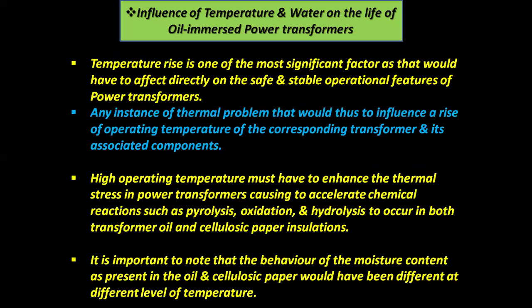Now, influence of temperature and water on the life of oil immersed power transformers. Temperature rise is one of the most significant factors, as it directly affects the safe and stable operational features of power transformers. Any instance of thermal problem would influence a rise of operating temperature of the corresponding transformer and its associated components. High operating temperature enhances the thermal stress in power transformers, accelerating chemical reactions such as pyrolysis, oxidation and hydrolysis in both transformer oil and cellulosic paper insulation.